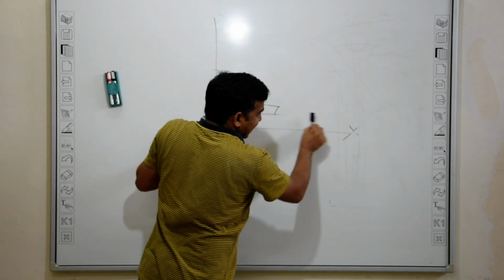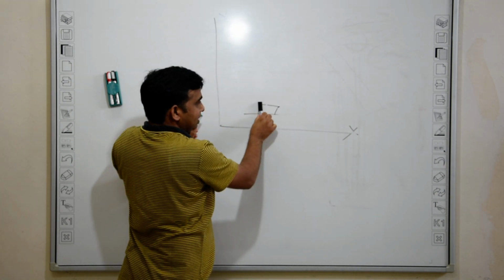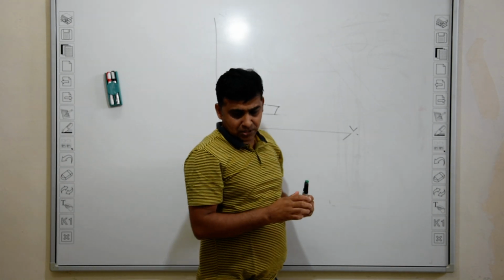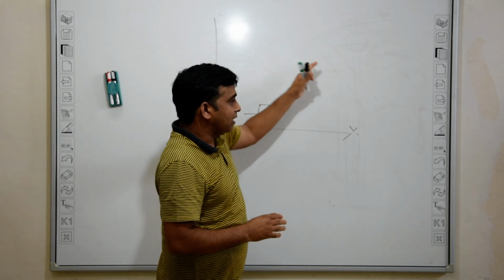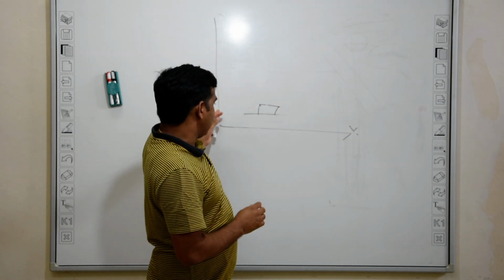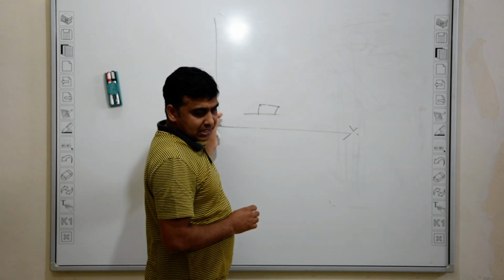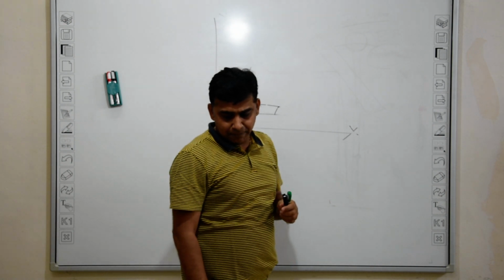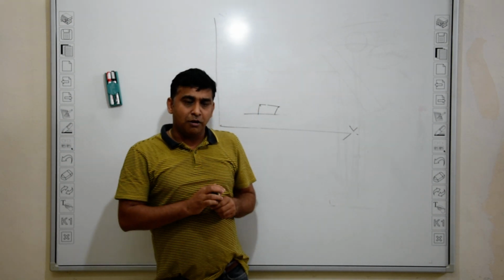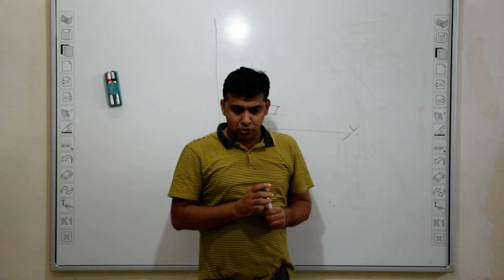So only when they are scanning is data collected. So there is less chance or no chance of a fuzzy image. In this way we are able to get the 3D image, and the coming back to the origin of the oscillating mirror is called the flyback. So this is the principle of confocal microscopy.